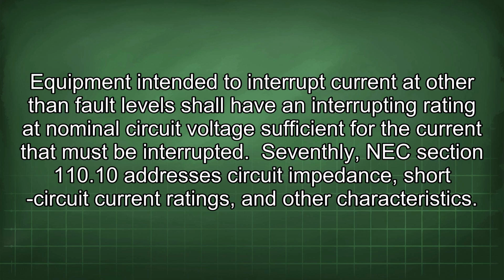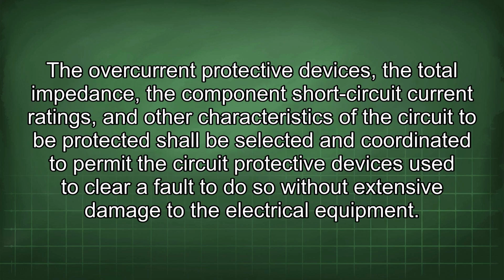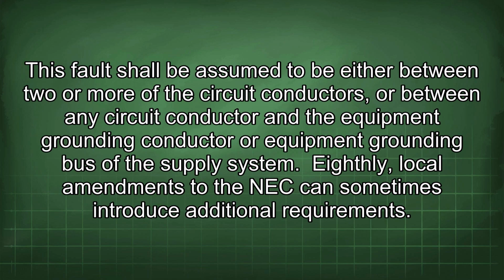Seventhly, NEC section 110.10 addresses circuit impedance, short circuit current ratings, and other characteristics. The overcurrent protective devices, the total impedance, the component short circuit current ratings, and other characteristics of the circuit to be protected shall be selected and coordinated to permit the circuit protective devices used to clear a fault to do so without extensive damage to the electrical equipment. This fault shall be assumed to be either between two or more of the circuit conductors, or between any circuit conductor and the equipment grounding conductor or equipment grounding bus of the supply system.